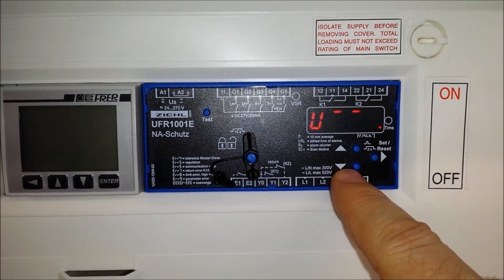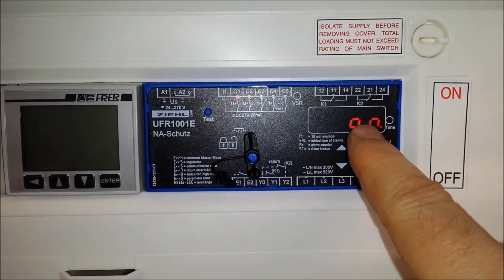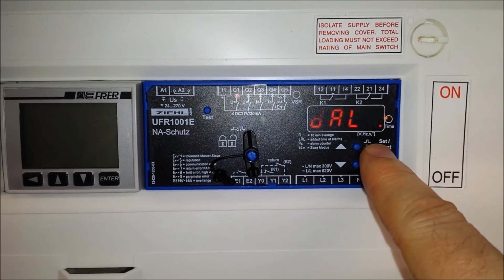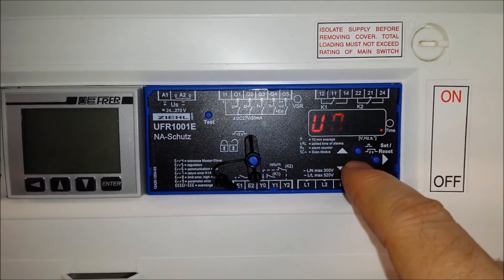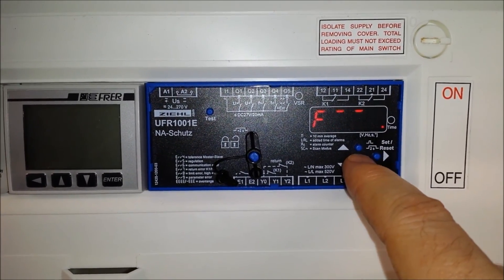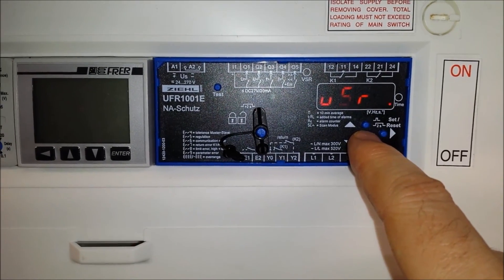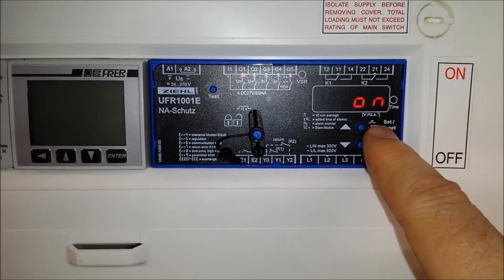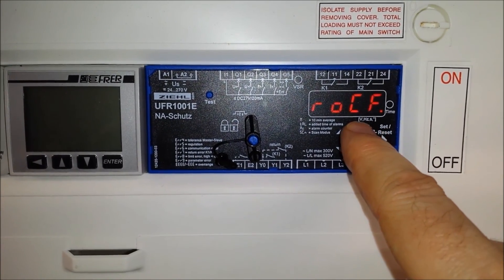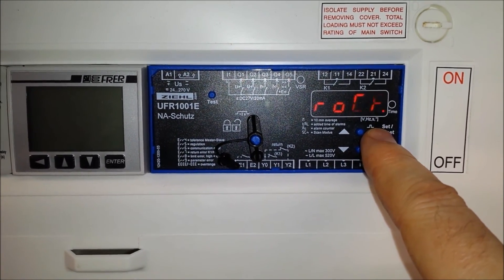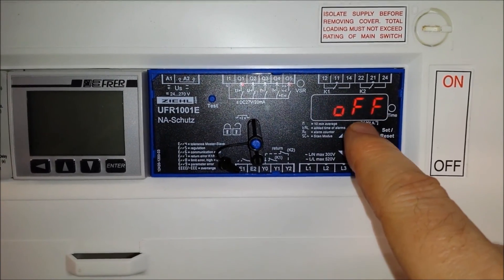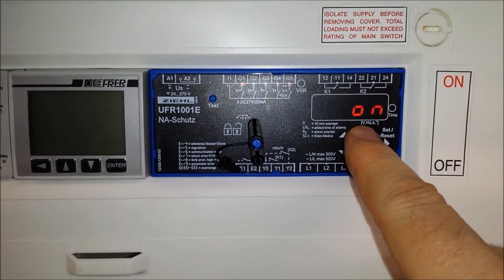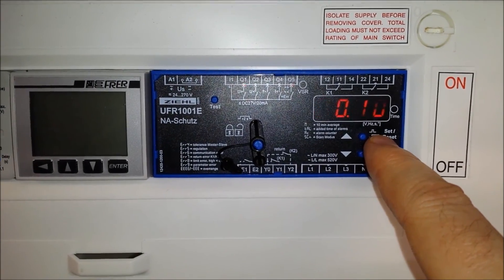As you may have noticed, any one of the values can be on or off every time. And we will come down and take a look at our friend ROCOF. Not everyone requires ROCOF, so you can turn the ROCOF off. So you don't have to worry about having nuisance trips because you've just wound the ROCOF up out of the way. So then if you go and look there, you can see now this ROCOF value is off. But if you want it on, you simply put it on again. Accept. And there's the ROCOF value back.